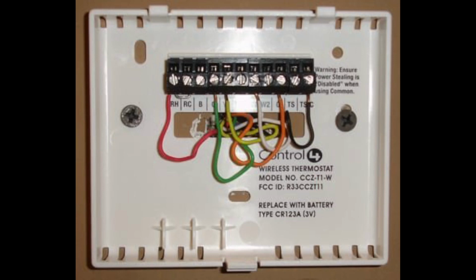And basically you'll come along with your common side on the control board, which will feed over and go into your B. That means your power and B, which is your common. You connect those, and this thermostat is now being operated by the transformer. You don't have to have a battery operation. A lot of people will do the batteries because it's just a little bit more simple for the homeowner, and you can actually still put the batteries in there for battery backup.